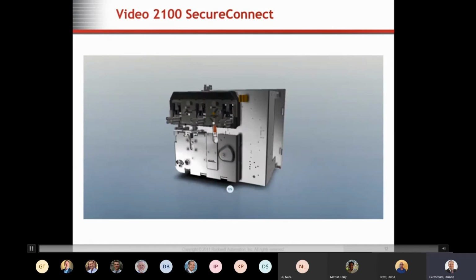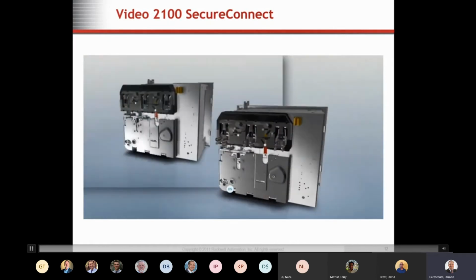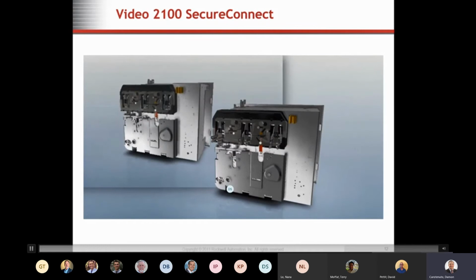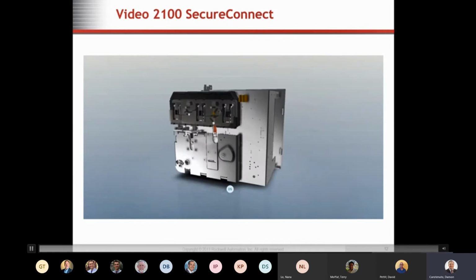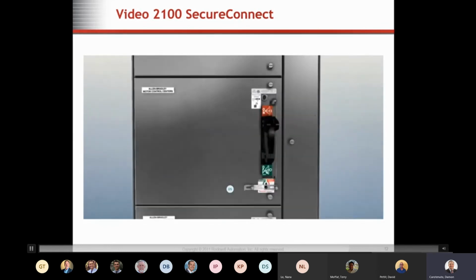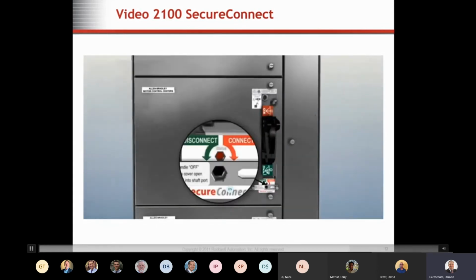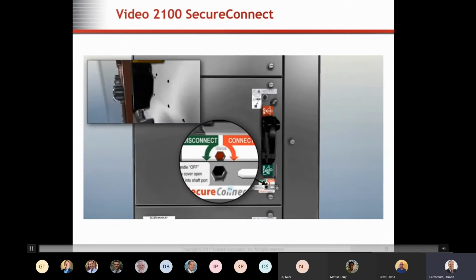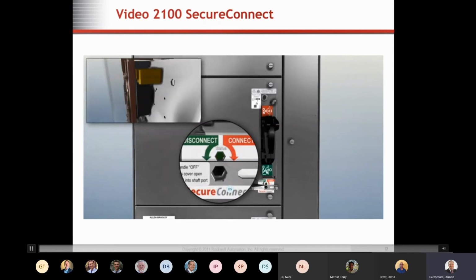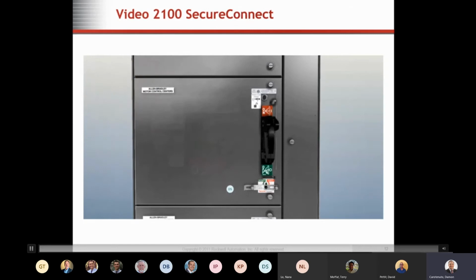To help increase electrical isolation, 2 sets of shutters close in front of the stabs, one set on the unit and the other on the vertical bus cover. A limit switch is also provided to indicate when the shutters are closed and that the stabs are not interfering with the closing of the shutters. A status indicator light on the front of the SecureConnect unit changes from red to green to inform the operator that the unit has been disconnected from the vertical bus.